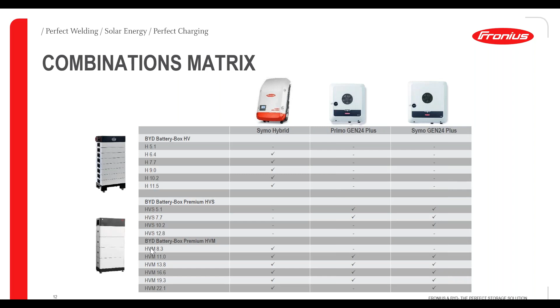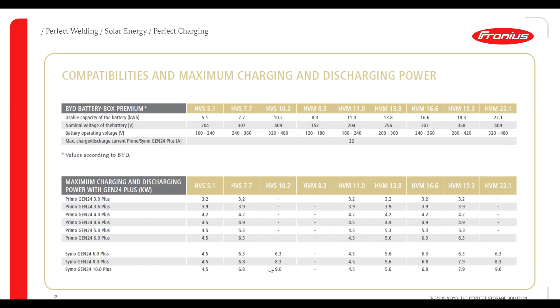When it comes to maximum charge and discharge power, there are different combination possibilities. If we have the Symo Gen 24 10 kilowatt combined with a BYD battery HVM 22.1 kilowatt hour, you can have a maximum charge and discharge of up to 9 kilowatts. Or with HVS 10.2 combined with Symo Gen 24 10, again we have a maximum of 9 kilowatts charge and discharge with this combination.